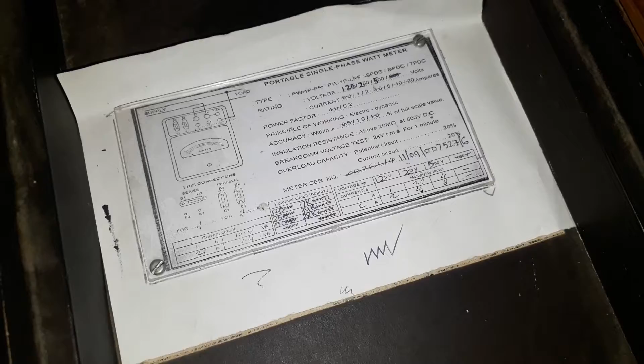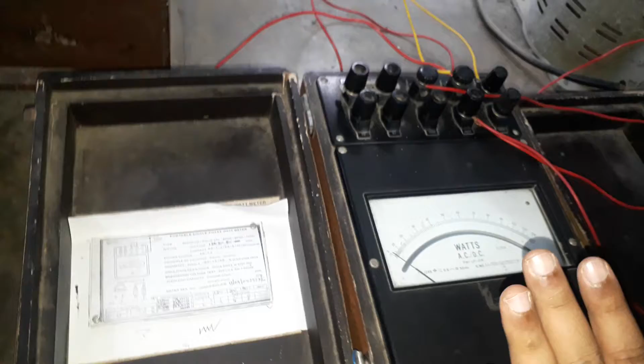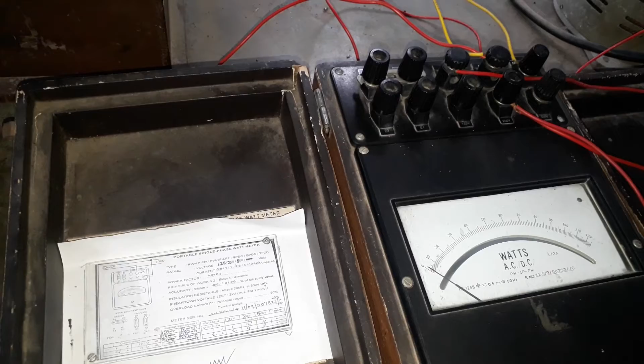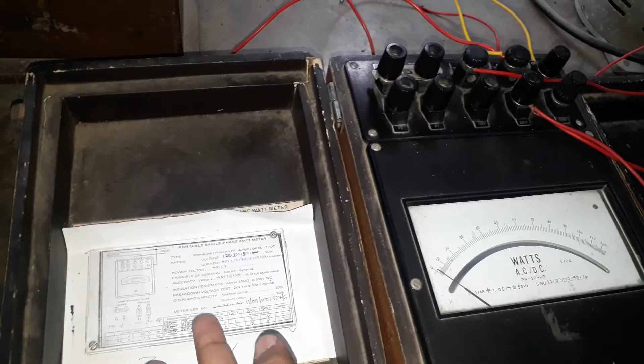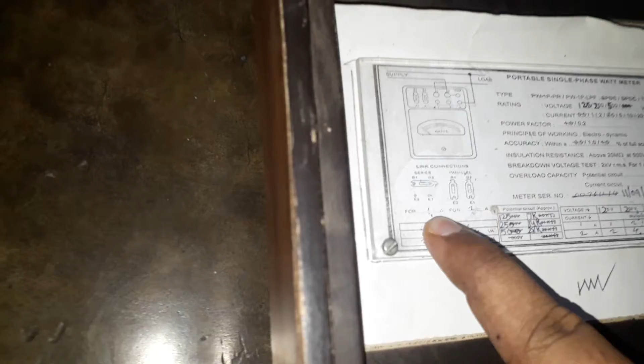Now going back to the circuit diagram, from the auto transformer we bring the supply first to the wattmeter. Whenever using a wattmeter, the foremost thing to be careful about is its multiplying factor, which is readily available here. As you can see, it depends on these strips, the coils, whether they are connected in series or parallel. These two strips are connected in series, so when connected in series, the current rating is 1 ampere, and there is a table given over here.